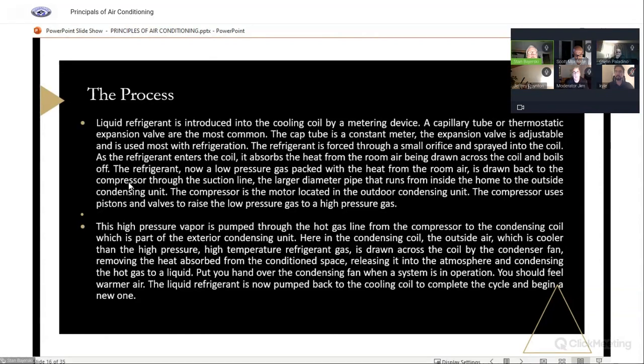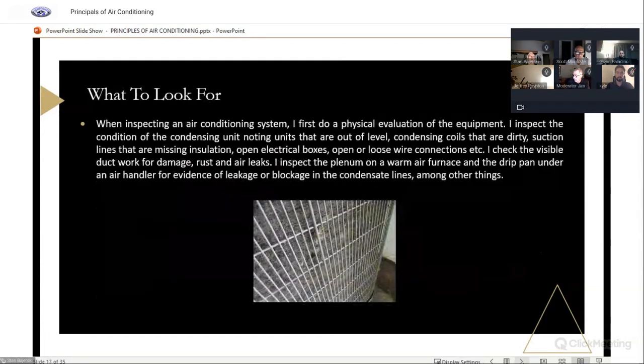The compressor uses pistons and valves to raise the pressure, from a lower pressure to a higher pressure gas, because we have to have it at a higher pressure to be able to condense it. When we move that to the condensing unit, by blowing air across that condensing coil, we are releasing that heat and turning it back into a liquid and pushing it back to the cooling coil and starting that cycle all over again. So it's a constant cycle: pick up the heat, get rid of the heat, pick up the heat. It's like a boiler. We're bringing the heat to the space and releasing it, bringing cooler air or water back to the furnace. So it's a very similar process. Kind of simple when you think about it, but a lot of things can affect it.